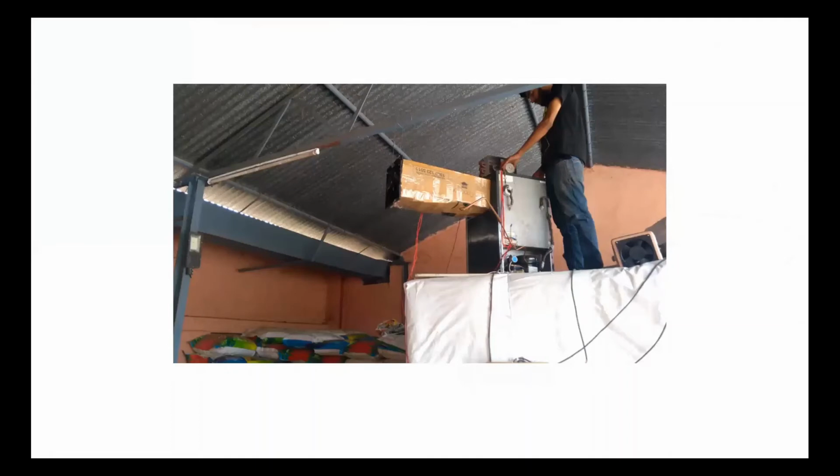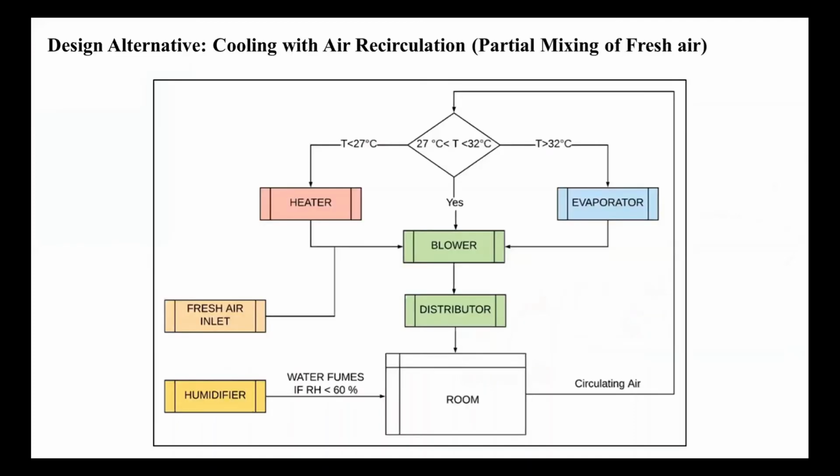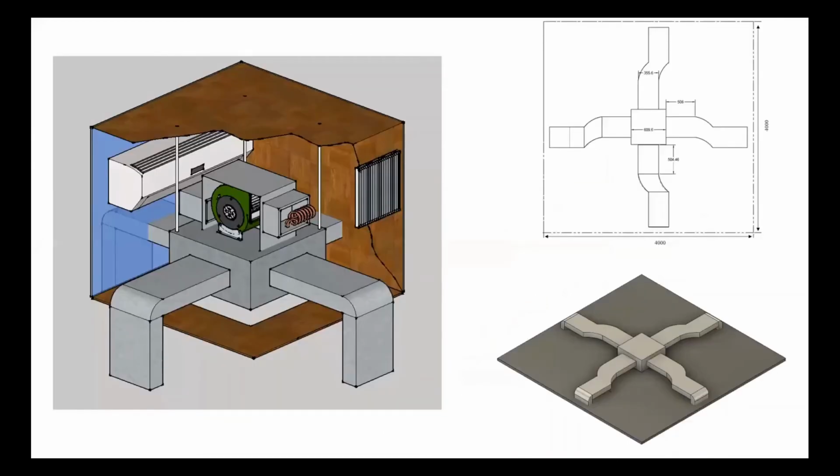Then we actually installed one full system in DOGR itself. The system is still there, if you can go there. There were many challenges when we were doing this, because of the challenge of maintaining not just temperature and relative humidity, but also making sure that you get a good amount of fresh air passed through the system, because onion is known for releasing gases that are troublesome. And so a lot of engineering was involved.